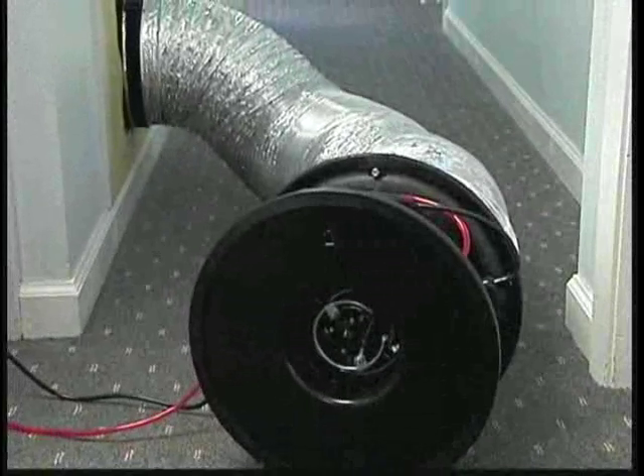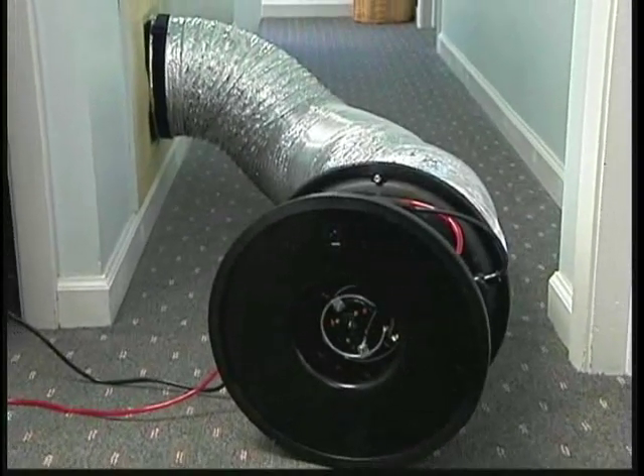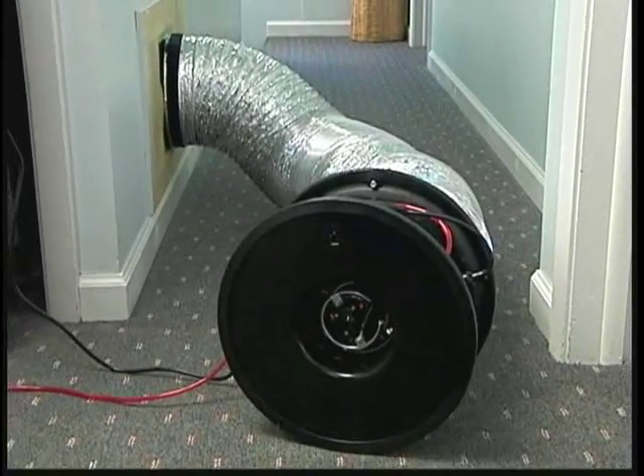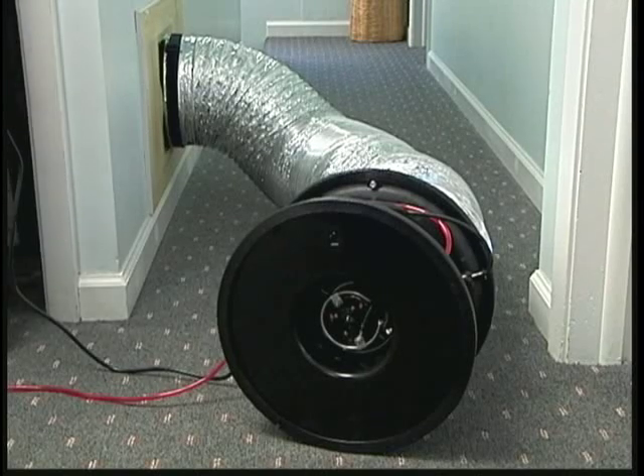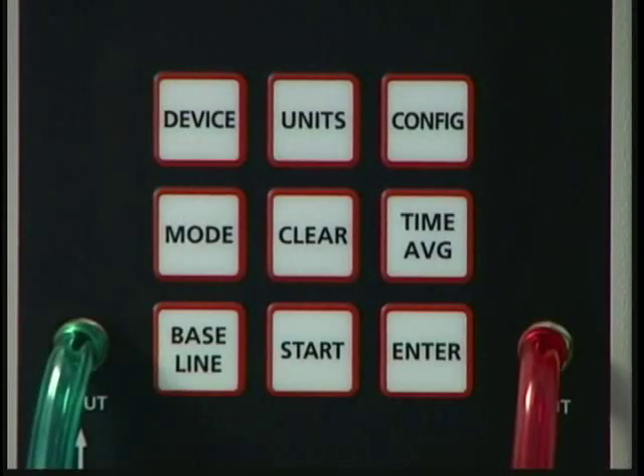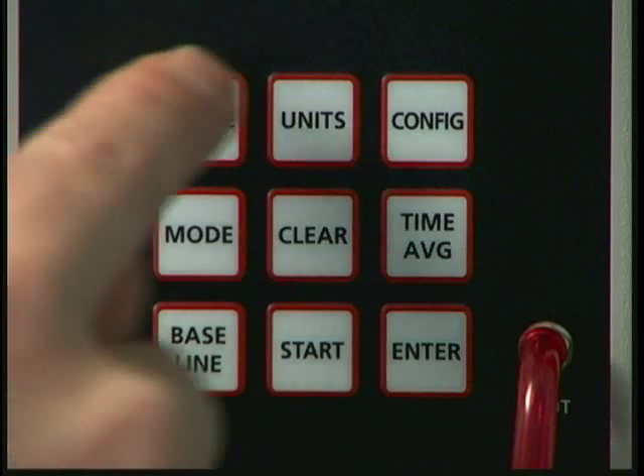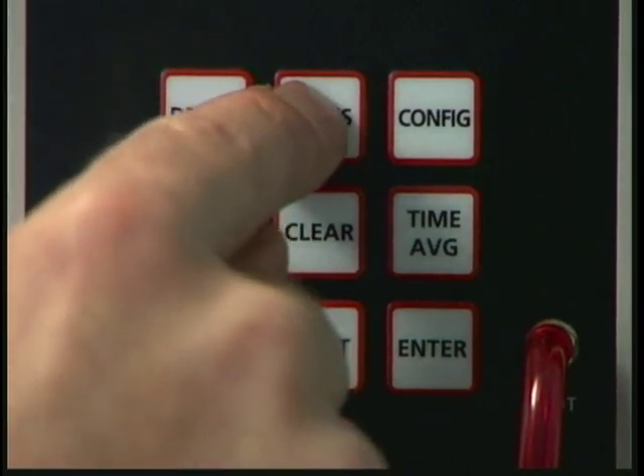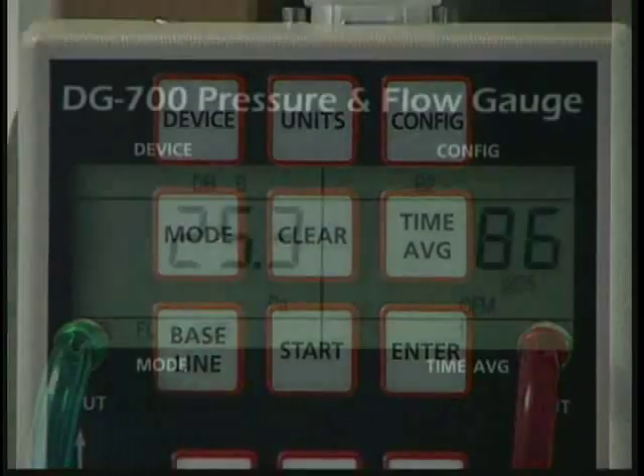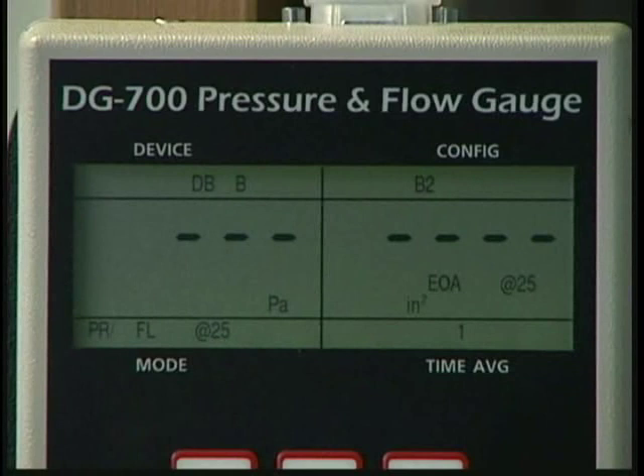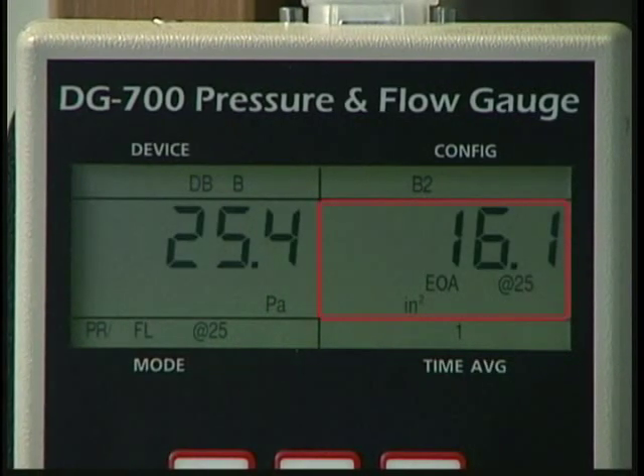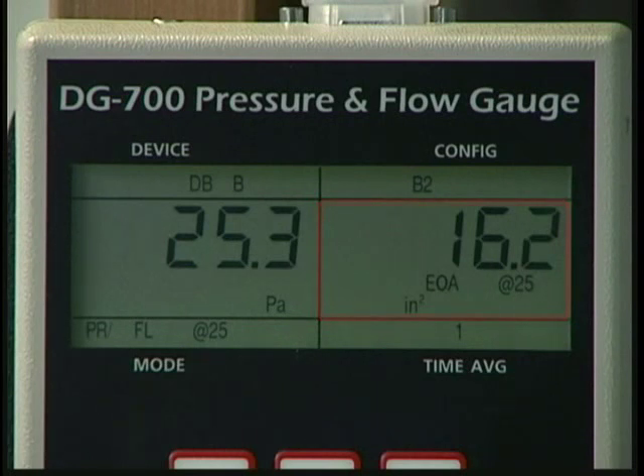Once you've determined the total leakage rate for the duct system, you can now estimate the leakage area of the duct system in square inches. This is done by pressing the units button three times while the Duct Blaster system continues to operate. In this demonstration, the gauge indicates that the duct system has a leakage area of approximately 16 square inches. The leakage area is a useful way to visualize the physical size of all the leaks in the duct system being tested.